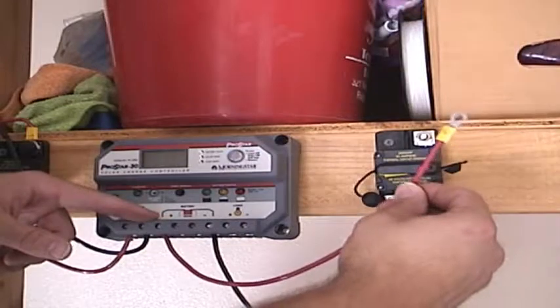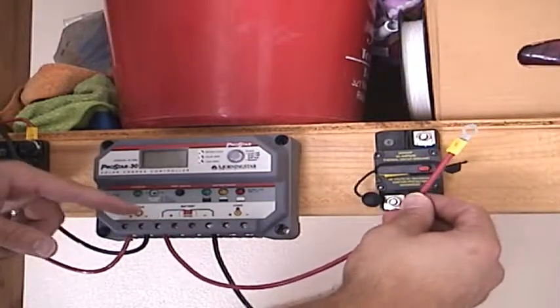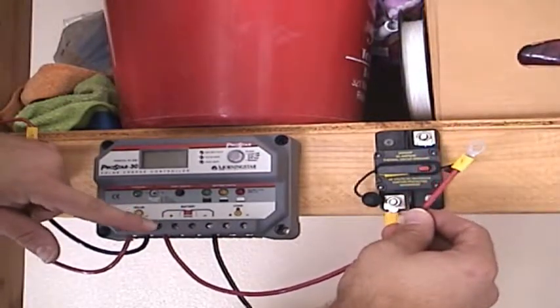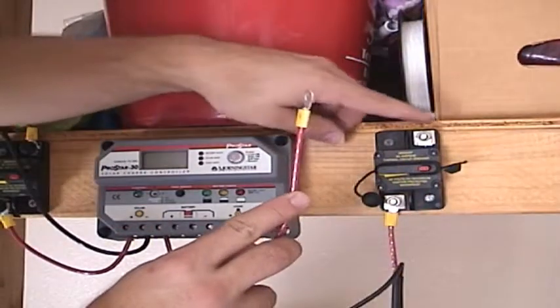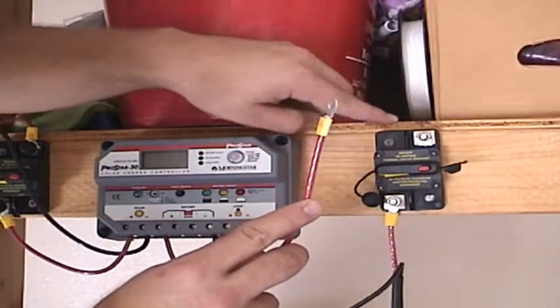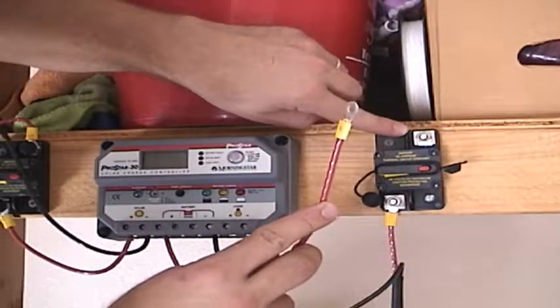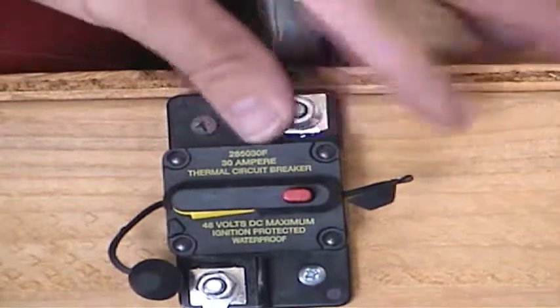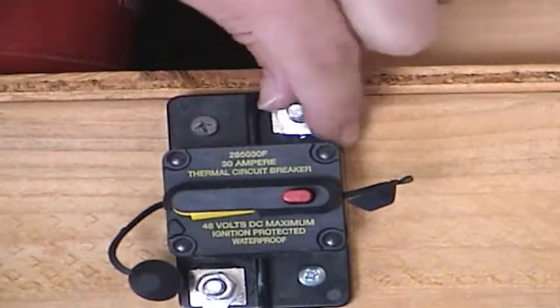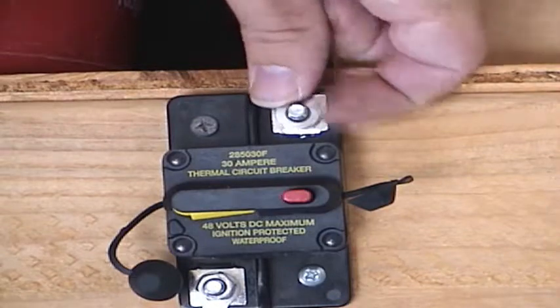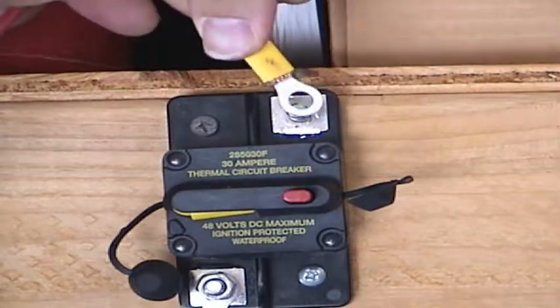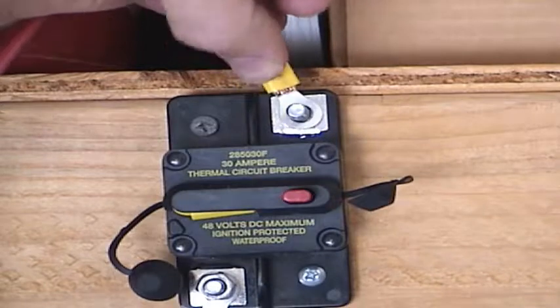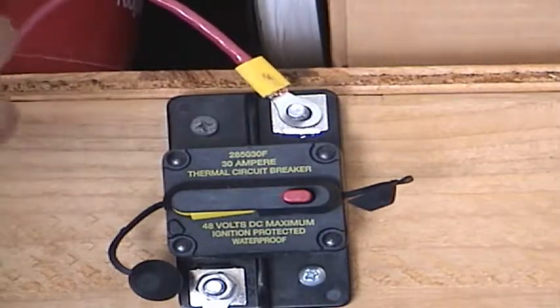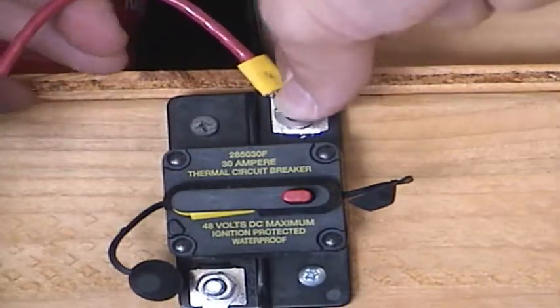And then we're going to take the 12-inch piece of red wire that's coming from the positive battery output and connect it to the top terminal on the circuit breaker, the terminal that is marked tab on the side. Let's remove the nut and the lock washer. We will insert the ring terminal over the circuit breaker terminal, replace the lock washer and the nut.